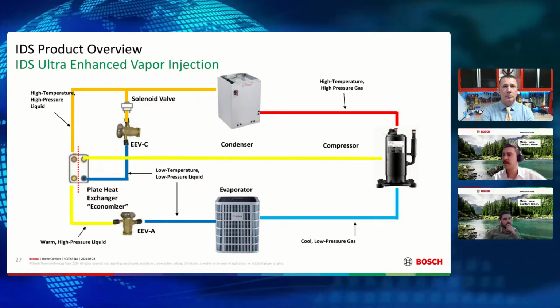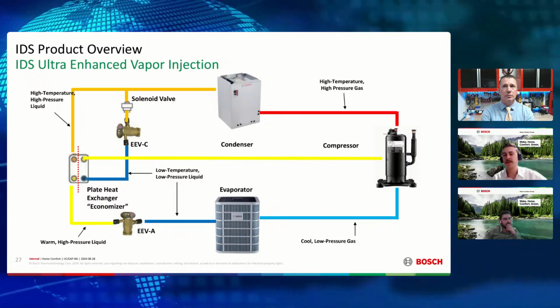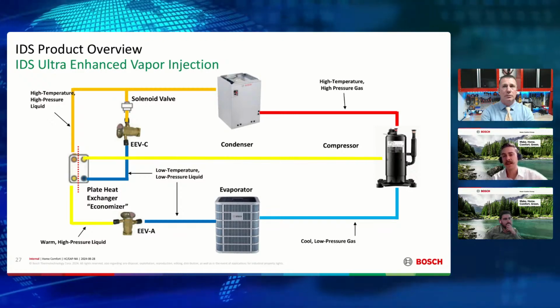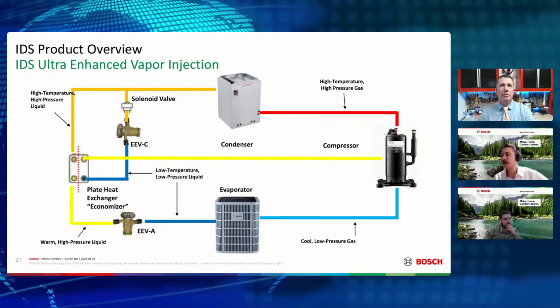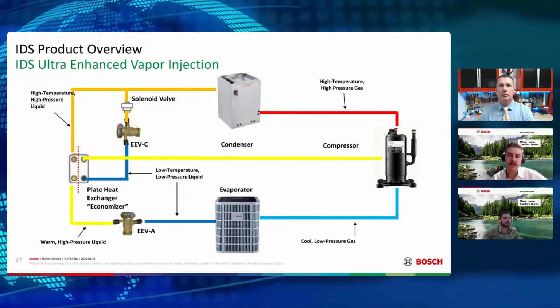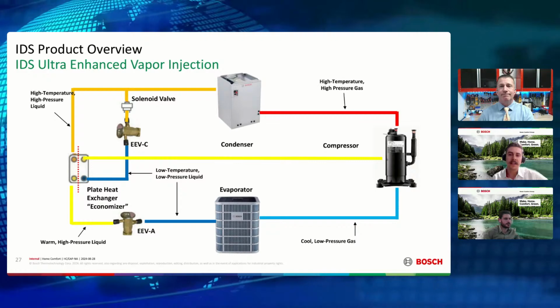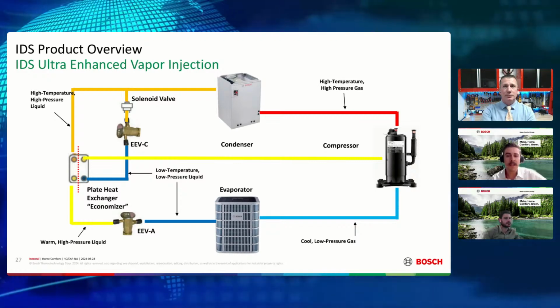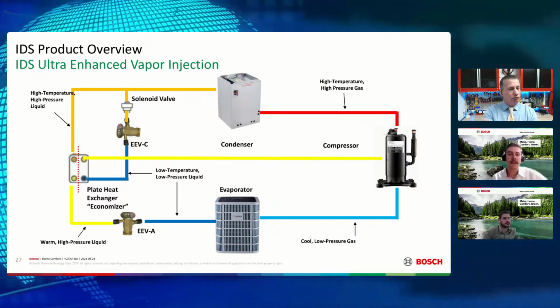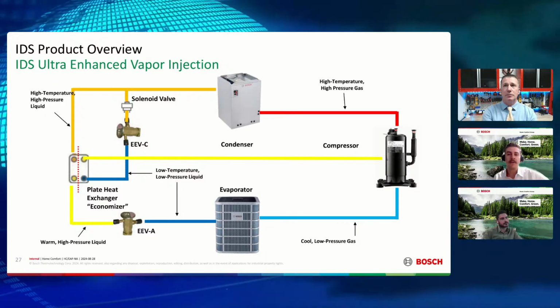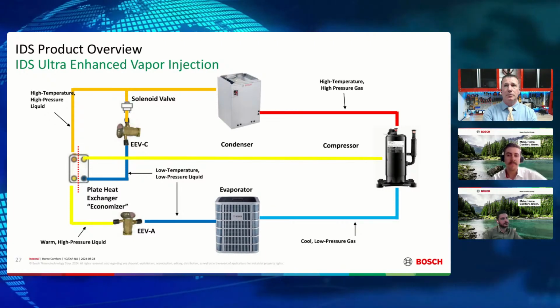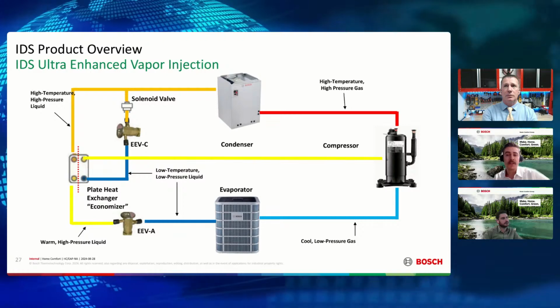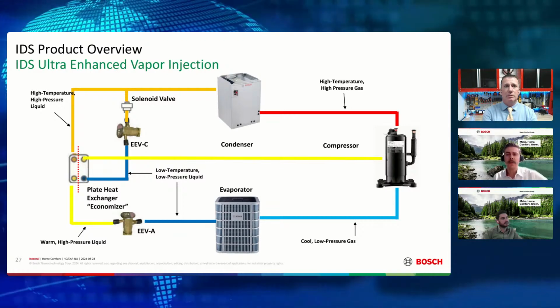If we look at a PH diagram, what we really want to do is expand its width. One way to do that is to increase our subcooling past the condenser. We don't want to do it in the condenser, because that would decrease our outlet temperature and our heat transfer would diminish as well.